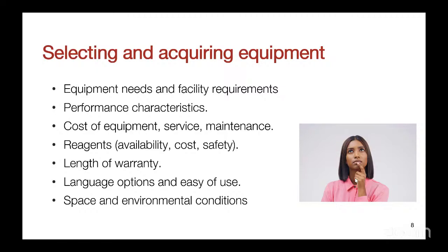Now, what will be the cost of the equipment, the services, the maintenance? Next, you need to also look at reagent availability, the cost of reagent and the safety of that reagent. What is the length of warranty? What are the language options? And is it easy to use? Then also you need to look at your space and the environmental condition.